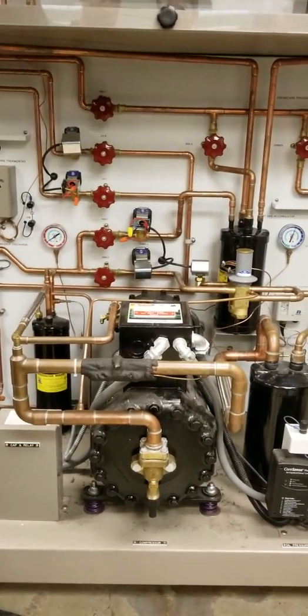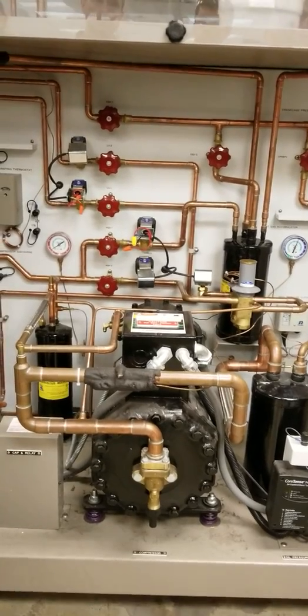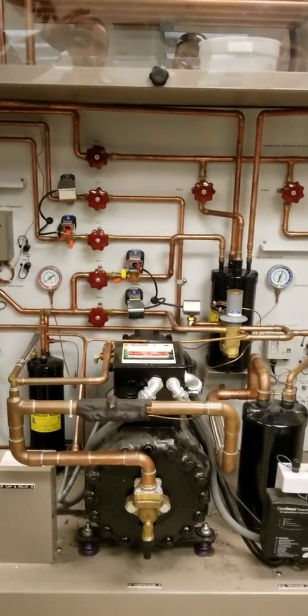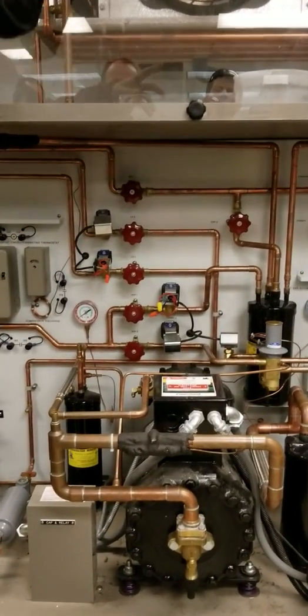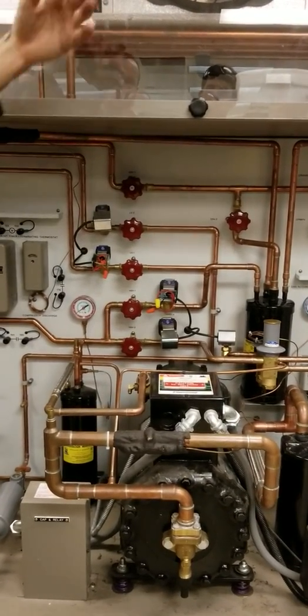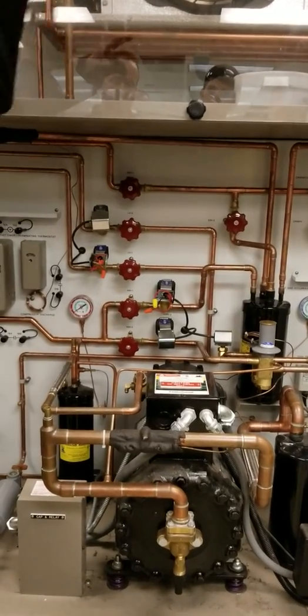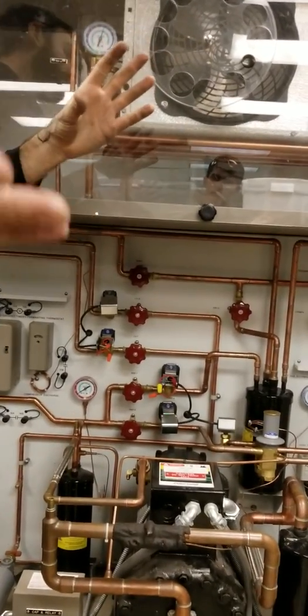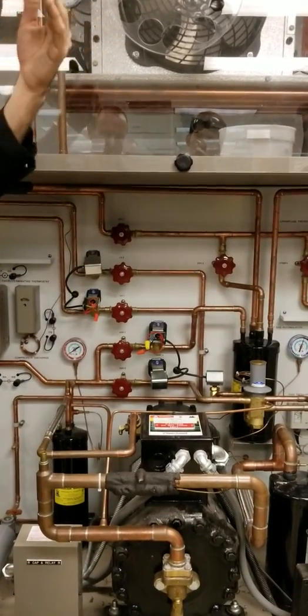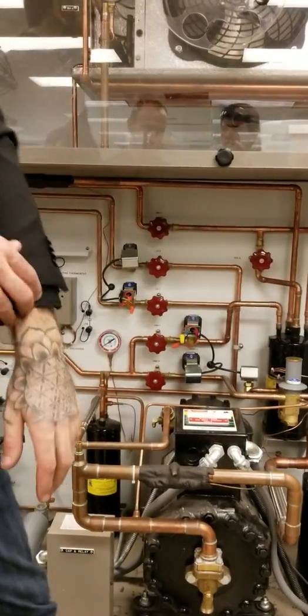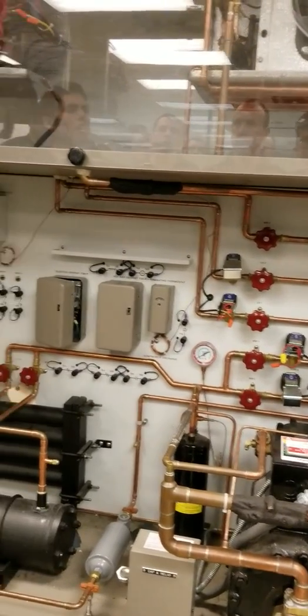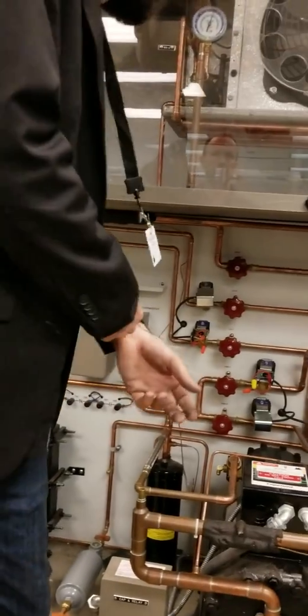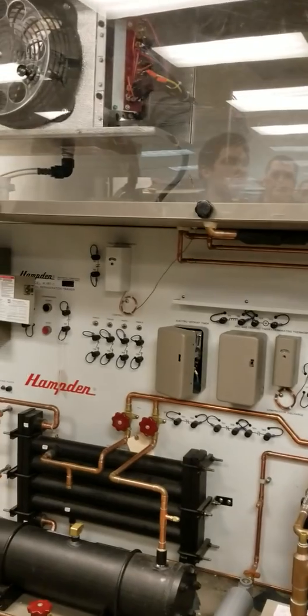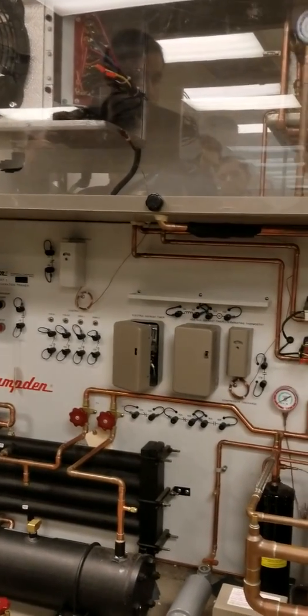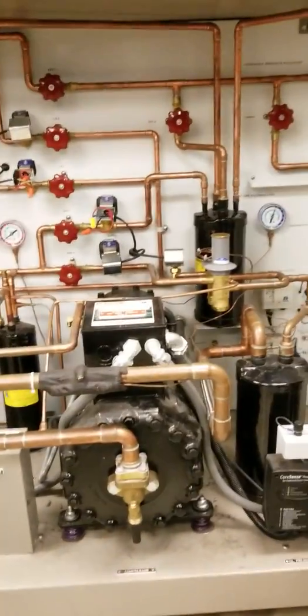So when pressure drops, let's say pressure in here is 12, it's going to keep that refrigerant in there at 12. Pressure is going to spill in, it's going to build up a little bit. It's going to get up to 15, it gets up to 20, it gets up to 30, and as soon as it hits 35 and then 36, it might allow some of that psi out. As soon as the pressure inside the evaporator will be stronger than the spring pressure that was set. 40 though? For a residential unit. For this, we're probably getting down to right around 5 to 10 degrees. This thing's running at. So what about those high-end? Okay, so good, thank you.